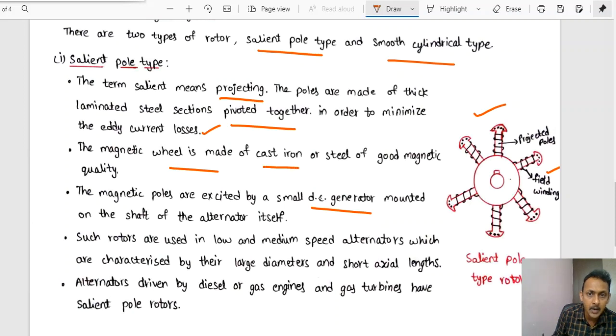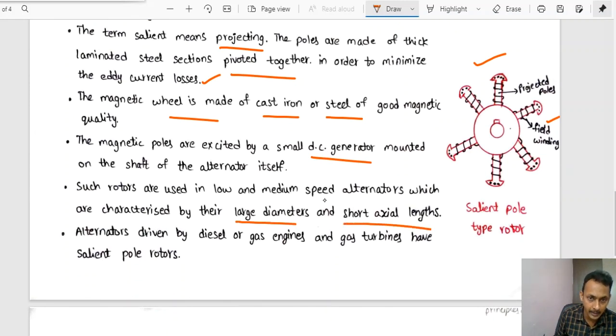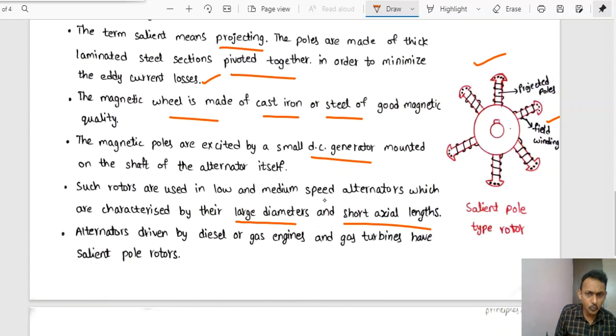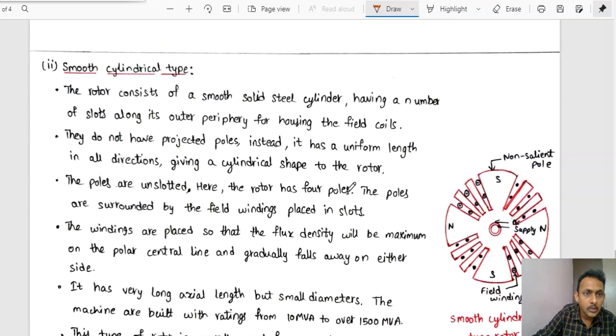The magnetic wheel is made of cast steel or cast iron with good magnetic quality. Salient pole type rotors are used in medium-speed alternators, characterized by a large diameter and short axial length. Most of the time, alternators driven by diesel engines, gas engines, and gas turbines use salient pole type rotors.